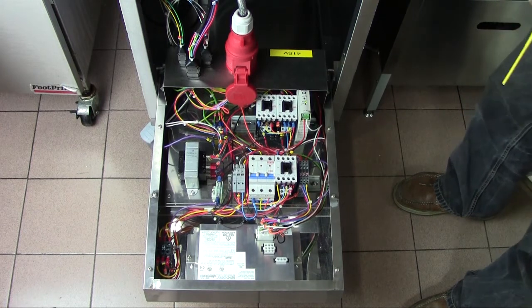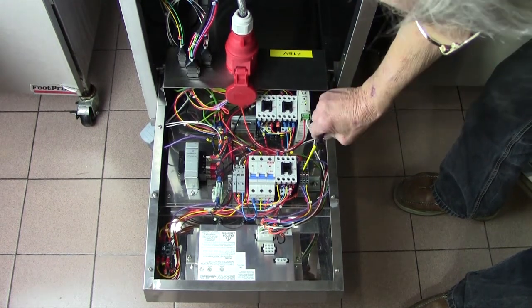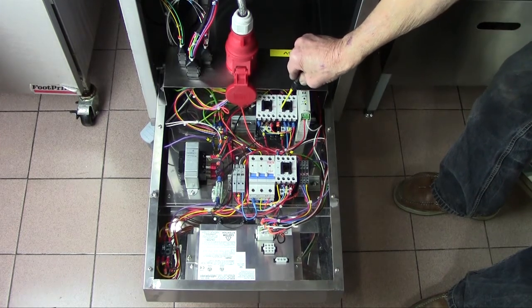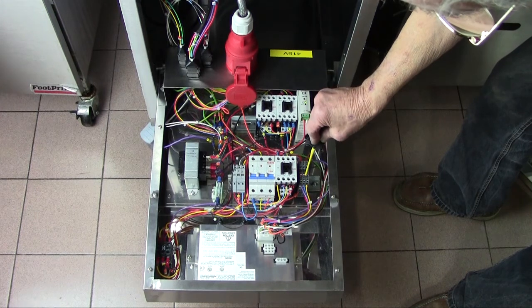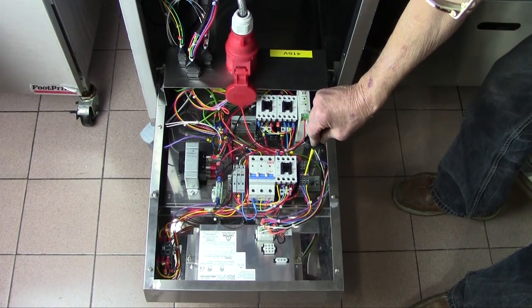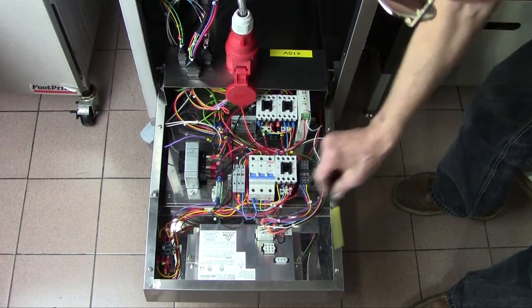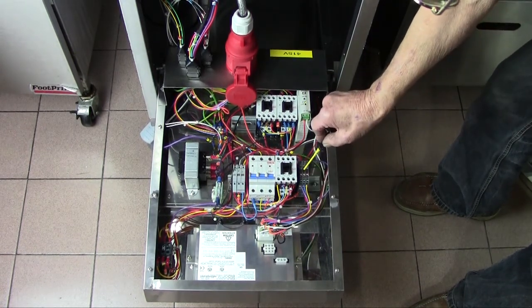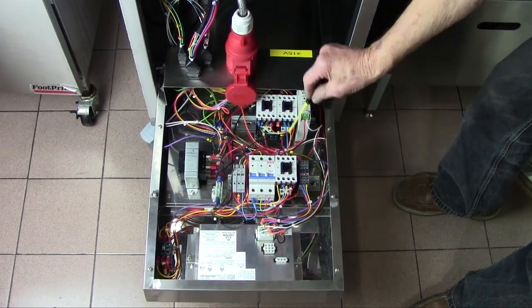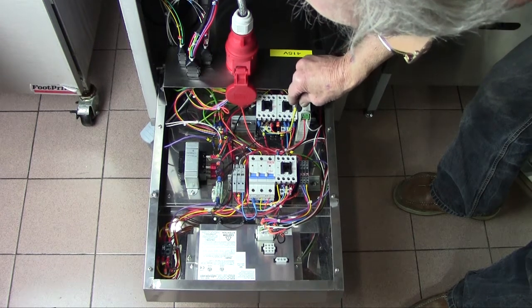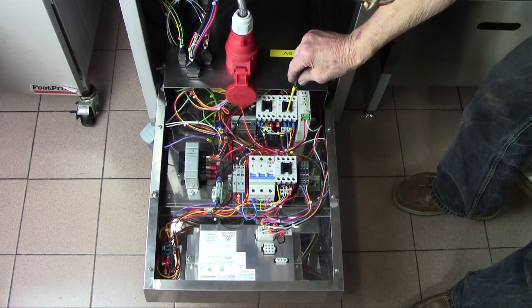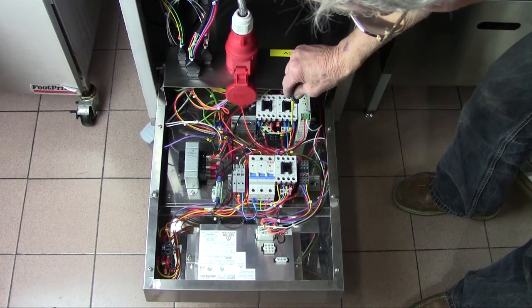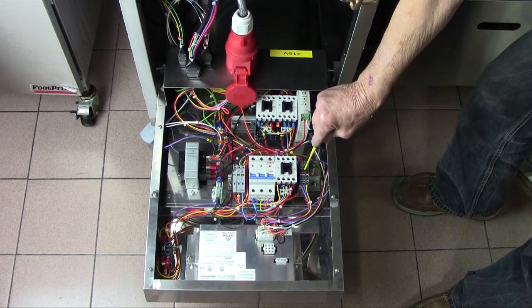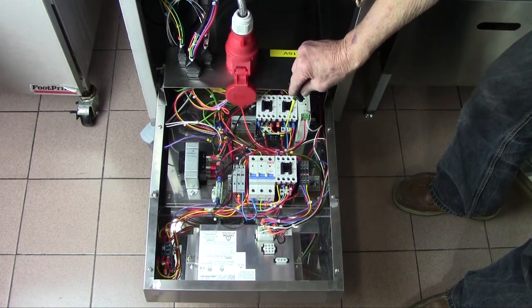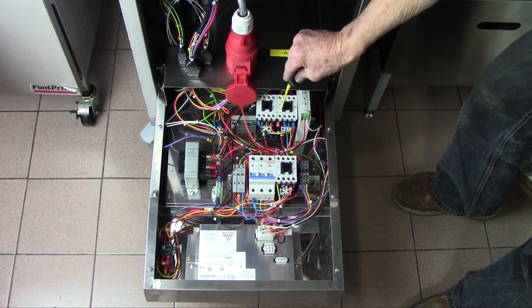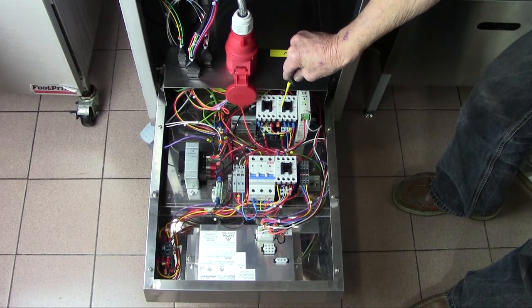If the low message is shown, check the relays and the contactors as shown previously. The difference being that if there is no voltage to the relay, replace the control board. If there is a message from the control board and the relay is activated, check that it's activating the voltage on the coil of the contactor. If the contactor is not receiving any voltage, replace the relay. If the relay is sending voltage to the contactor and the contactor is not activating, replace the contactor.